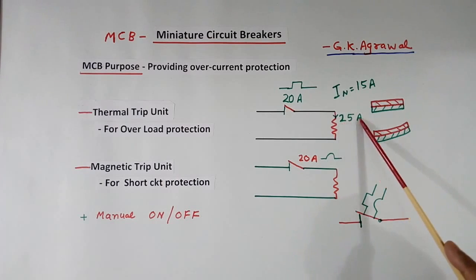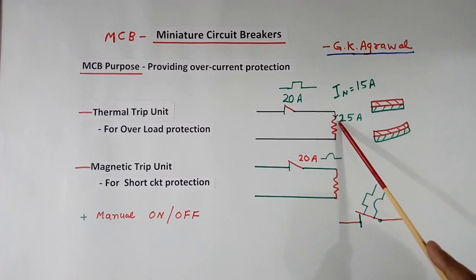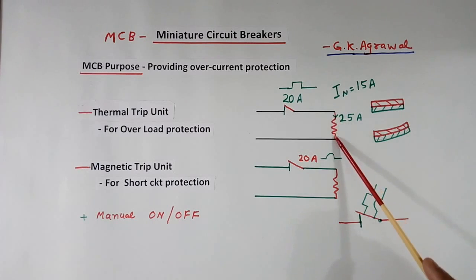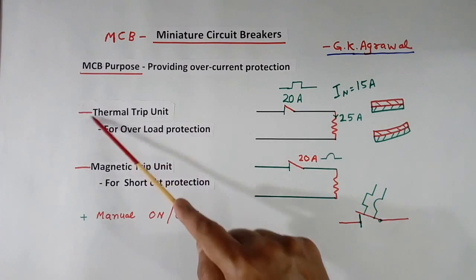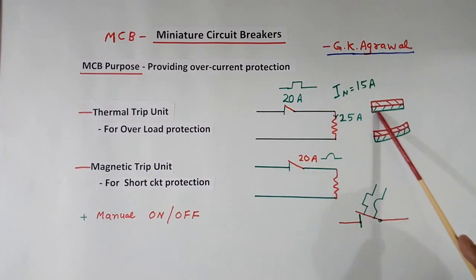But load current is more because of some reason. I have shown a resistor, it may be something else also. When more current flows in the thermal trip unit, there will be a bi-metal strip which will get heated up. It consists of 2 different metals. When it gets heated up, it will bend and the connection will open.